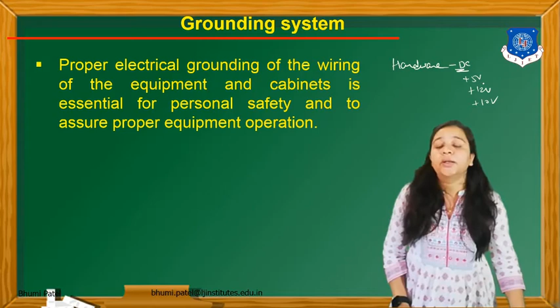If we connect different types of PLC hardware, suppose this is my other devices connected with this plant, and this is my PLC. We can connect the PLC with proper grounding, and also connect the other devices with another proper grounding. So we can apply individual grounding systems for the PLC as well as the other system. This is the best method to apply a grounding system with the PLC hardware as well as other devices.